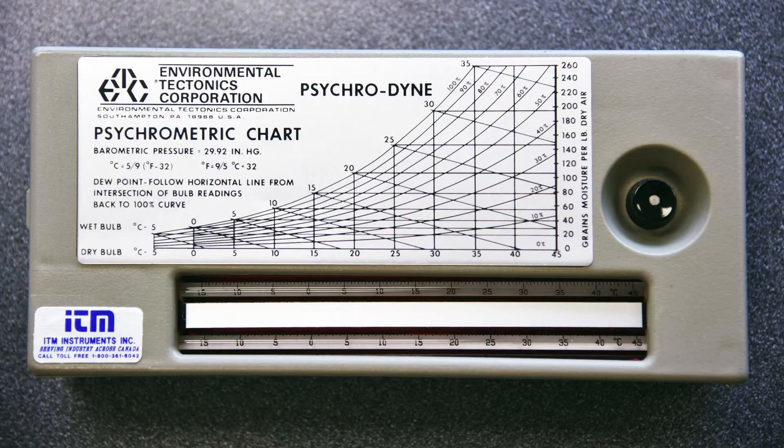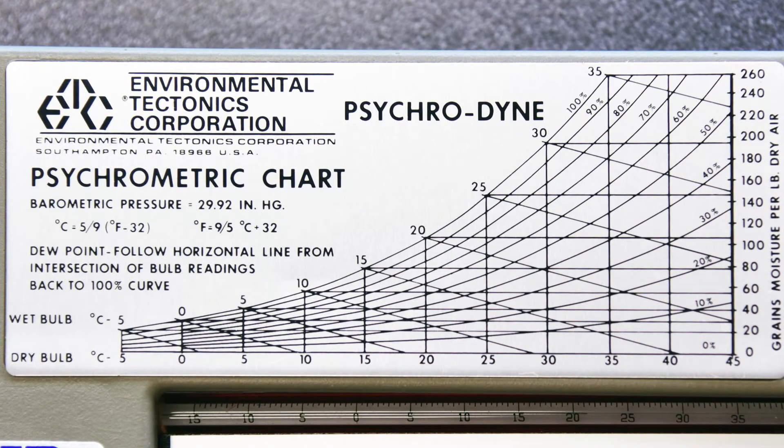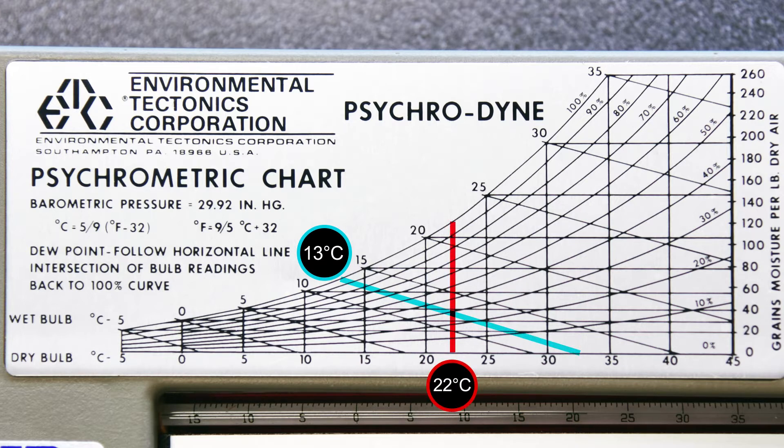For an approximate relative humidity reading of the space, you can use a psychrometric chart. There is one on the front of the psychrometer. Follow the diagonal line for the wet bulb temperature and the vertical line for the dry bulb temperature to find the point where they intersect. The value of the curved line at this point is the relative humidity.